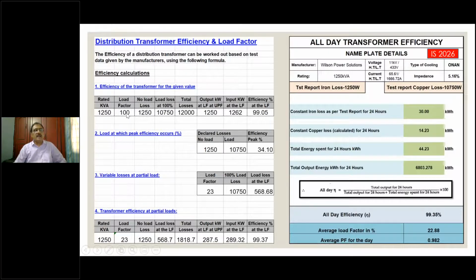The transformer at 100% load, fully loaded, will have 12 kilowatt losses. 1250 is the output, and the input would be 1262 based on the losses. That 12 kilowatt loss gives an efficiency of 99.05%. Whereas when you operate this transformer at a 23% load factor, the variable losses reduce so much that the efficiency is 99.37%. So at partial load, as you already noticed from the graph, the efficiency of this transformer is much higher. This facility can continue to expand, putting in additional wards, rooms and facilities until they reach around 50 to 60% load factor, and their efficiency will be almost 99.3 to 99.37%.